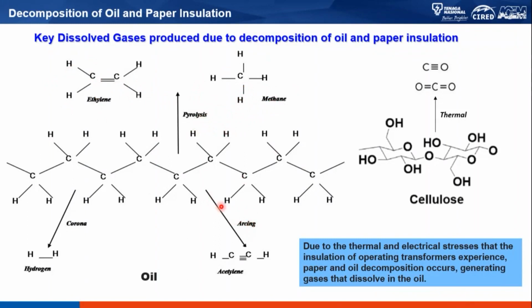If there is arcing inside the transformer, it will cause the structure to break, and acetylene gas, C2H2, will be generated inside the transformer in the oil itself. And if there is partial discharge or corona, it will generate hydrogen. Somehow, when a fault is generated inside the transformer, it is very repeatable. This repeatability is very, very useful, because we can use this information not only on one transformer but on the whole population of transformers, because the patterns are there.